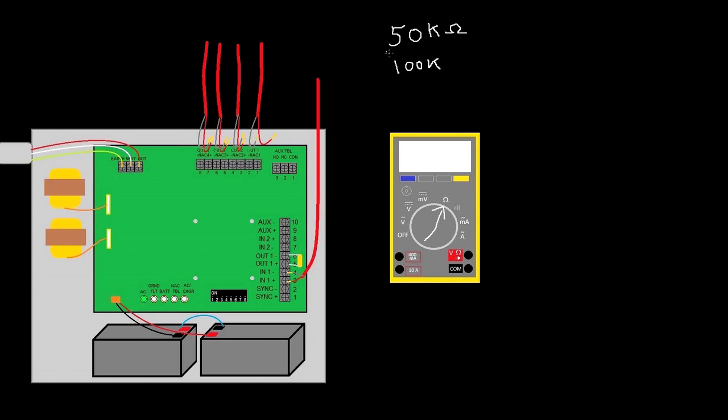Now the closer that is to a meg, the less true that probably is. If you had 900K, your panel may not go into ground fault, but you could probably find it and fix the problem. There's probably something going on there.